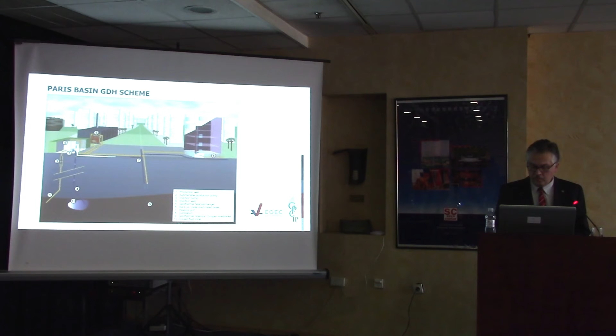If you look at the load duration curve in the Paris area for a typical district heating doublet, you can see that the yearly renewable energy source coverage is 66%, assuming a COP of 4 for a heat pump. Why is 66% very important? Because by law, if you have a district heating system supplied by renewable energy, on this percentage you benefit from a VAT of 5.5% compared to 20% today. So it brings the customer a lower energy bill.